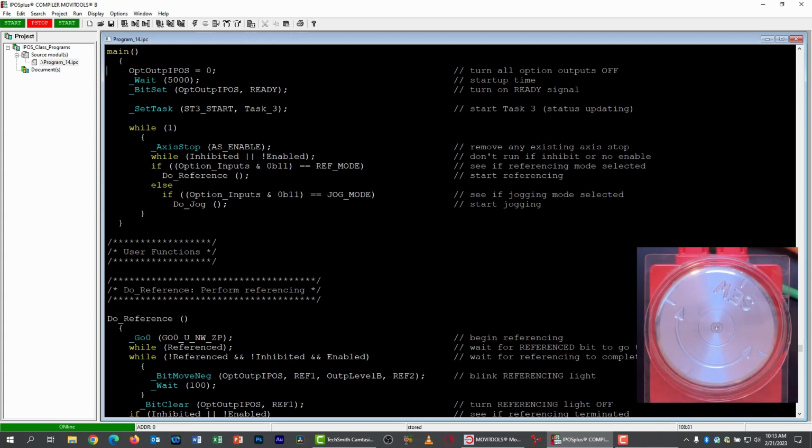All right, I have my control box. I'm going to go into jog mode by turning DI11 on now. You can see it's spinning just fine. Turn it off. Stops just fine, nice and quickly. Let's check the other direction. I'll turn DI12 from off to on, and then I'll turn DI11 back on. Jogs the other direction just fine too.